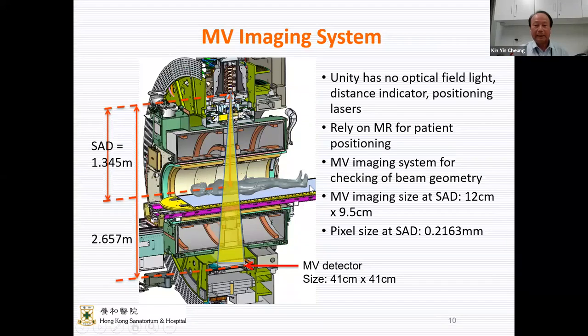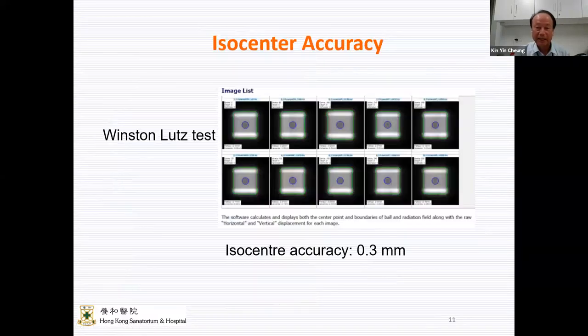As I said, it has a megavoltage imaging system, and this system is for alignment of the machine as well as for quality assurance. It's not for patient setup. You will find this useful in many aspects. For example, you can do a Winston-Lutz test to measure the isocenter accuracy. In our case, it's 0.3 millimeters.